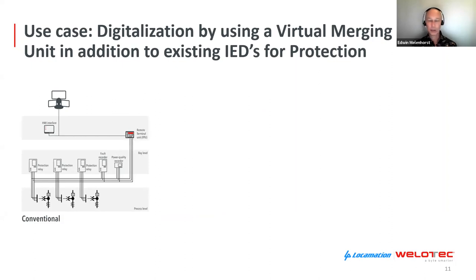Thank you. So how can we digitalize an existing substation with the virtual merging unit? Here we have a substation with some conventional protection relays, which are connected in a traditional way to the primary process. And we have an RTU to provide access to the substation for supervisory control and data acquisition by a remote control room. This situation still exists in many substations nowadays.